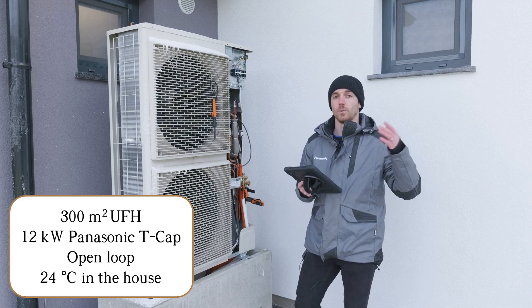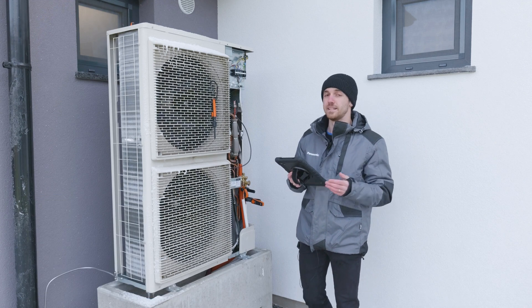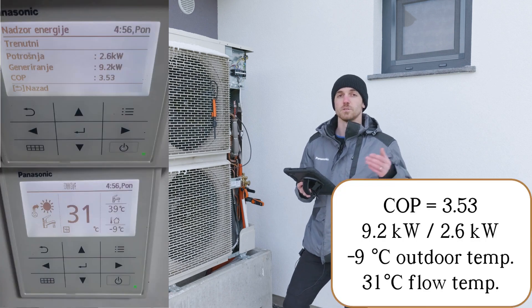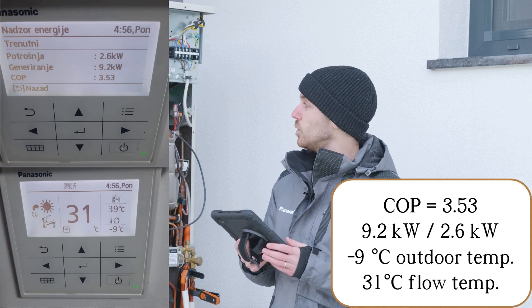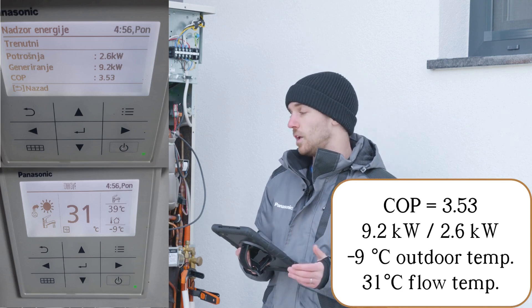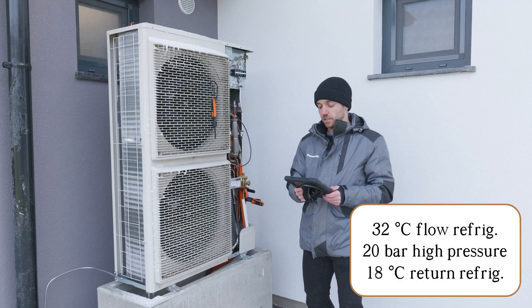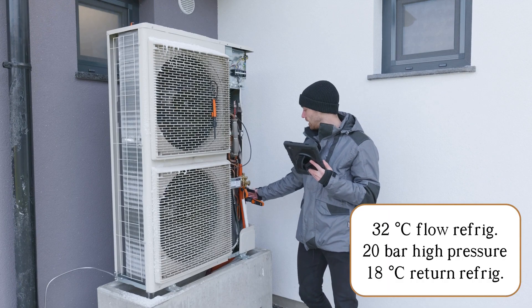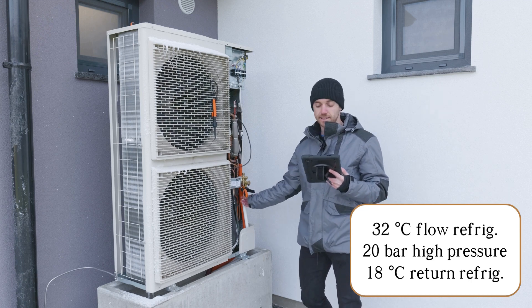In short, how it is working now — we are in a real situation where outdoor temperature is minus 5°C, and by night it was minus 10°C. COP was about 3, so really good numbers. We already had a few defrost cycles and analyzed what was going on. Currently we have measurements showing 32 degrees Celsius high temperature refrigerant and on the other side low temperature is 18 degrees.